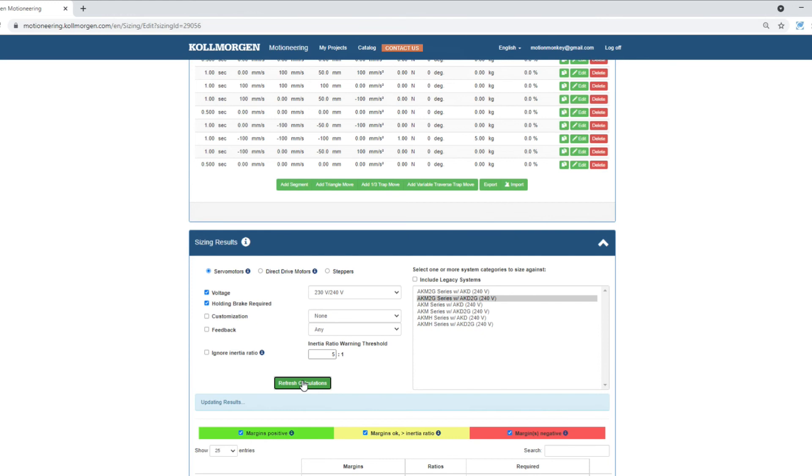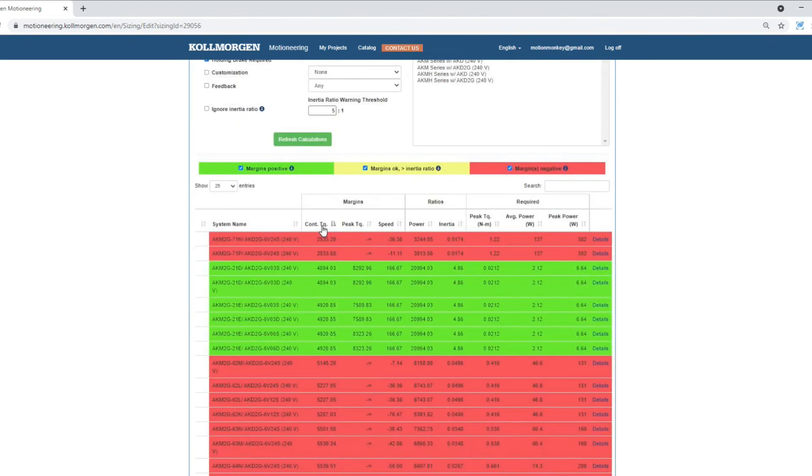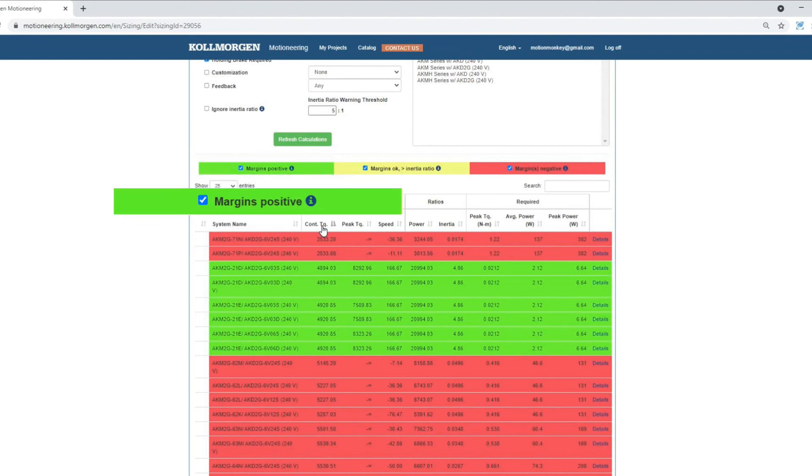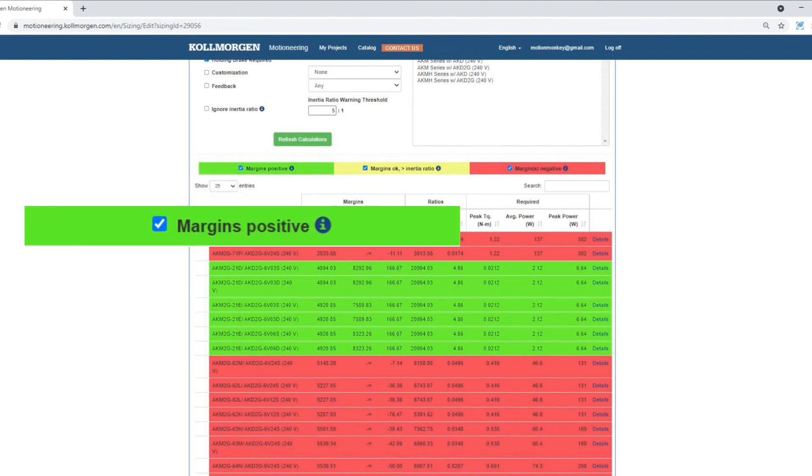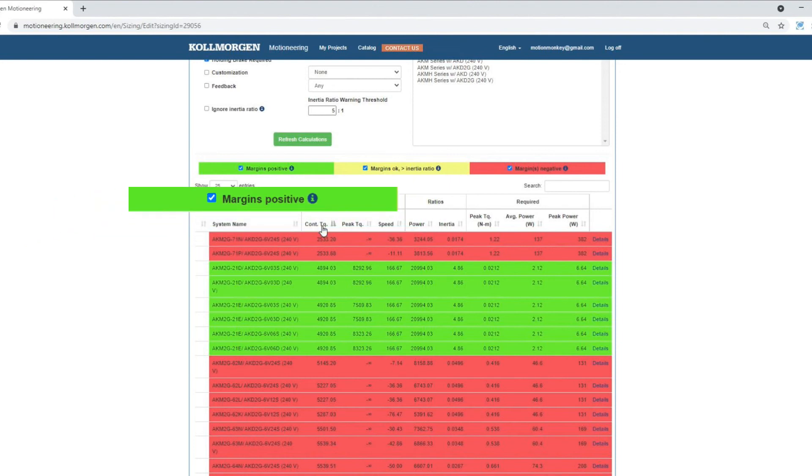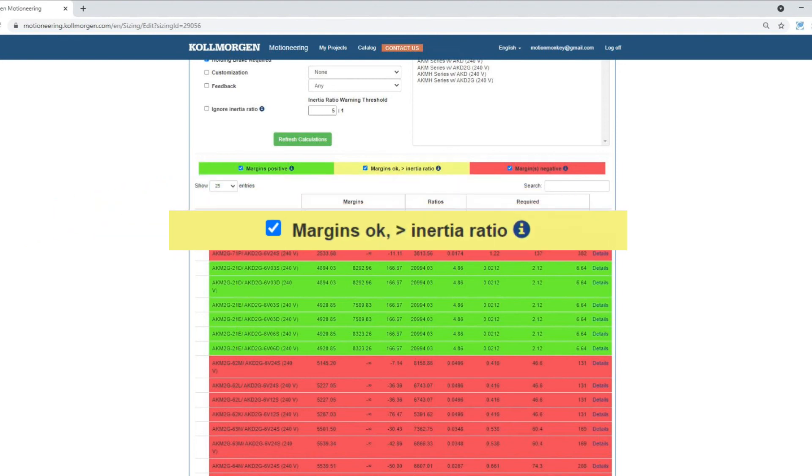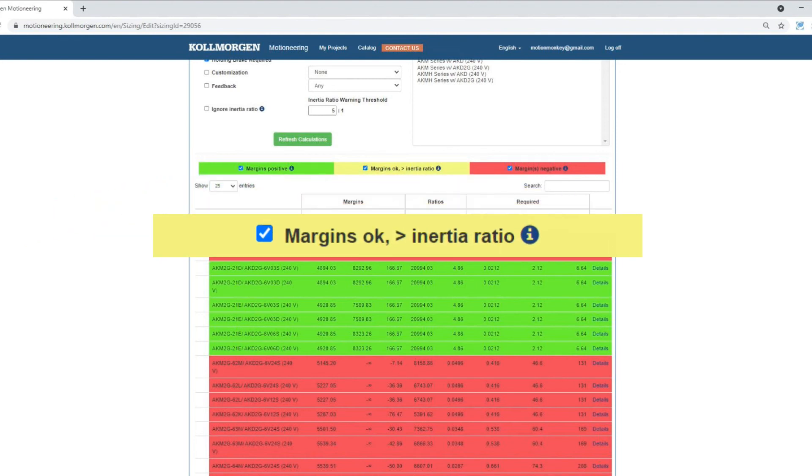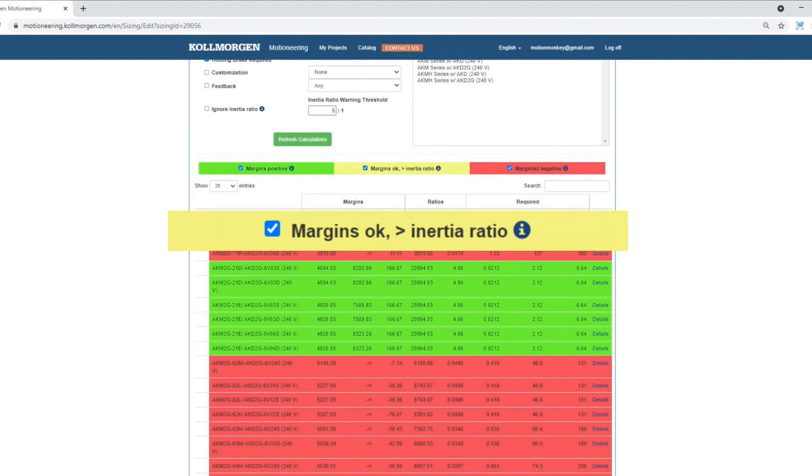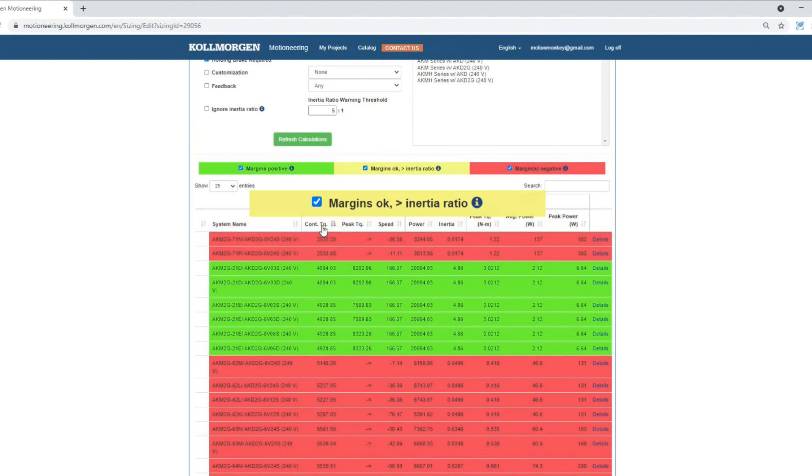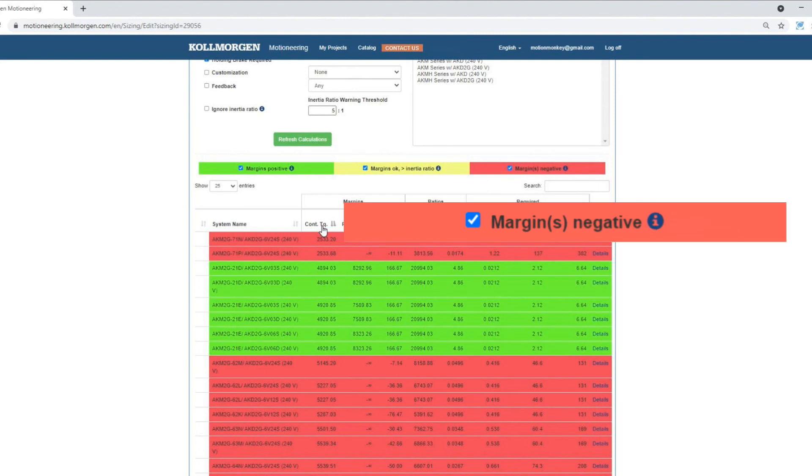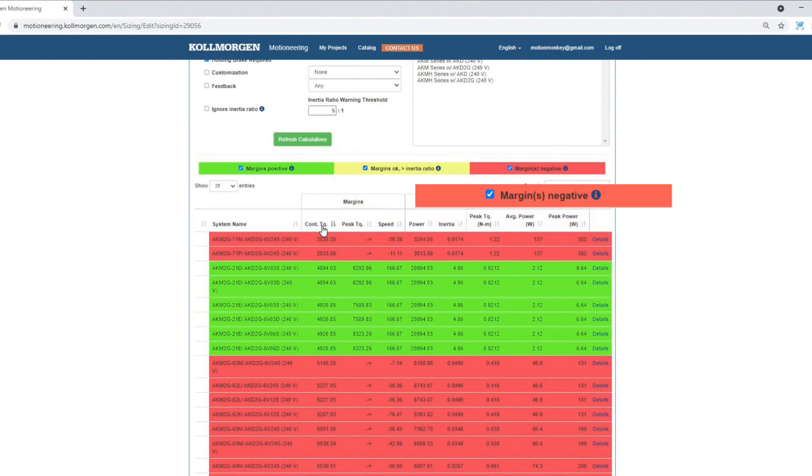Now, we can refresh the calculation. In the table, there will be systems highlighted in green, yellow, and red. Green meets all torque and velocity parameters. Yellow meets all the torque and velocity parameters, but is greater than the inertia ratio warning threshold that we set. Red means it does not meet either torque or velocity required.